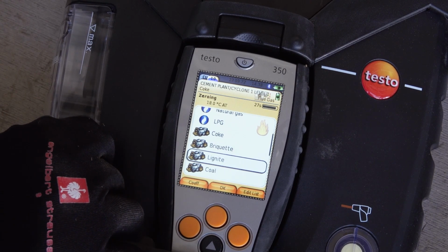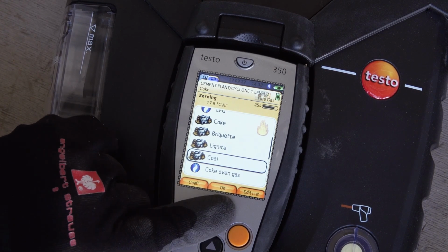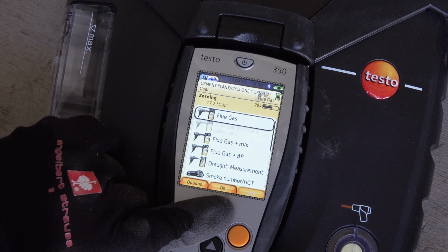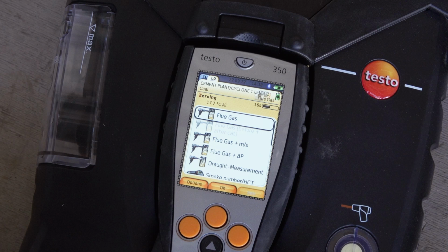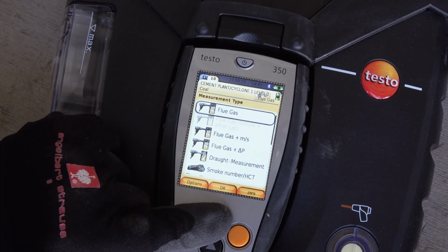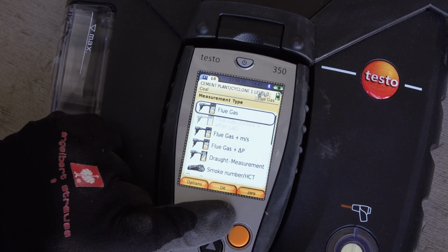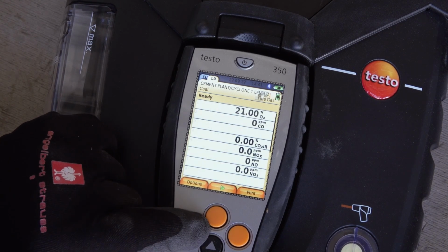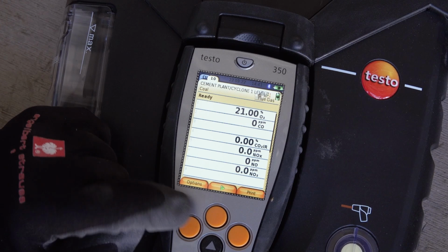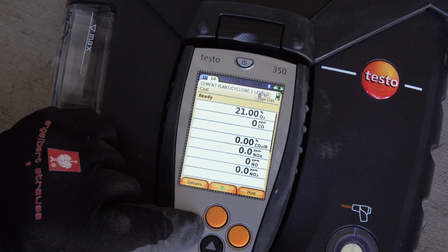Instructions in the display take the user through the measurement, so that no prior knowledge specific to the instrument is required. Thus, the Testo 350 is ready for use within a few minutes and the measurement can be started. Zeroing of the gas sensors is performed before a measurement. Zero point and drift of the sensors are checked. The O2 value is set to 21% O2. Make sure that the ambient air is free of interfering gases, e.g. CO or NO, during the zeroing phase.